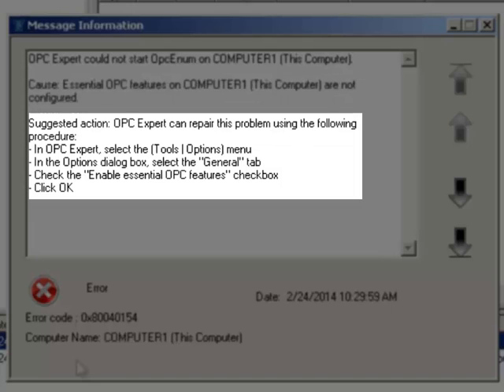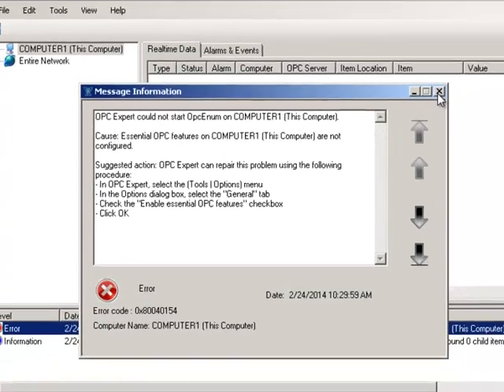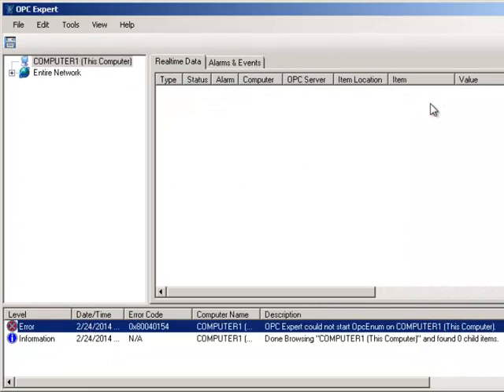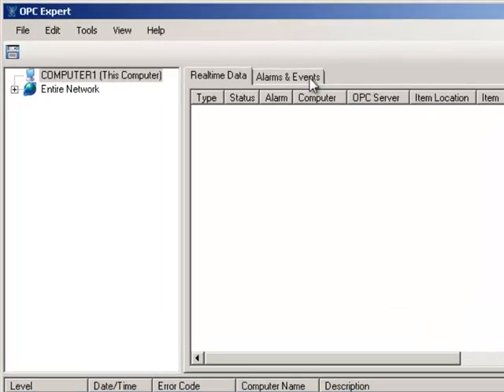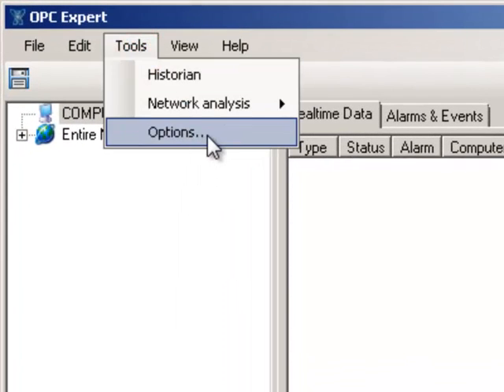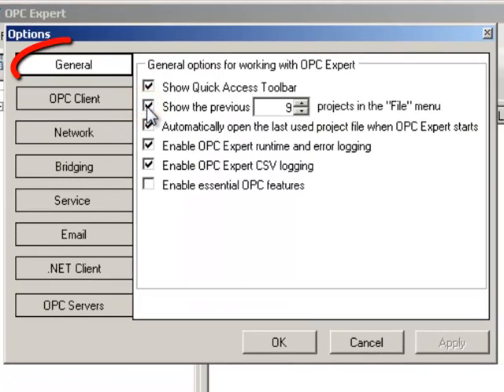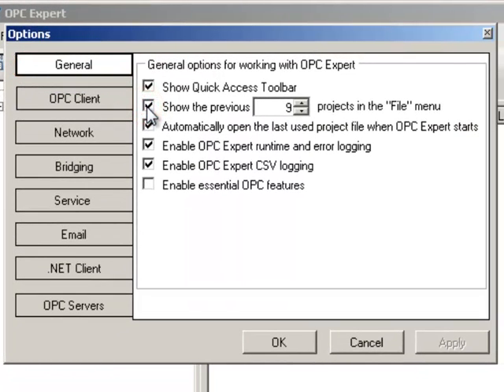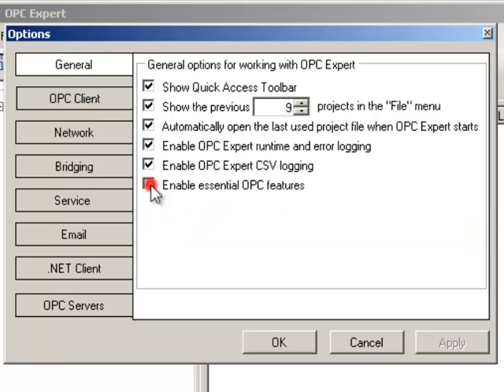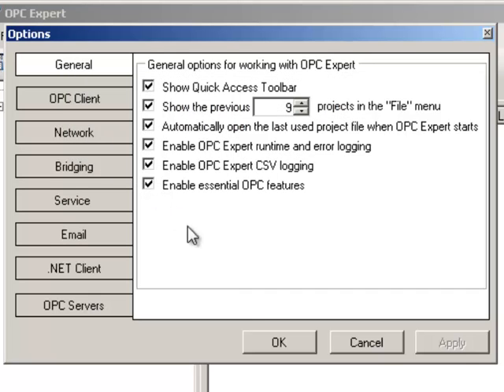OPC Expert can repair this error, so let's get it done. Close the Message Information box. In the menu, select Tools and then Options. In the Options dialog box, select the General tab. Check the Enable Essential OPC Features checkbox. OPC Expert will repair the Windows registry and configure OPC services properly. Click OK.